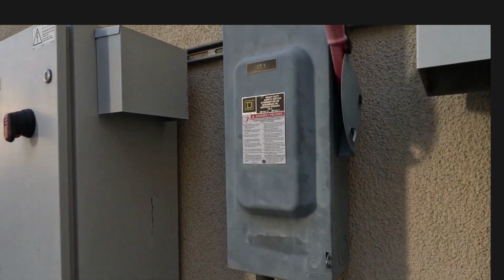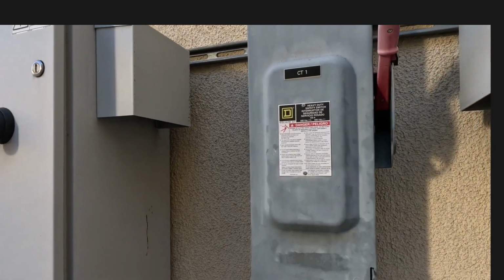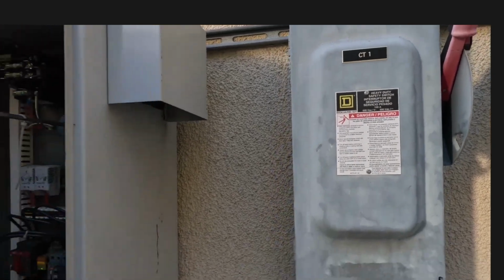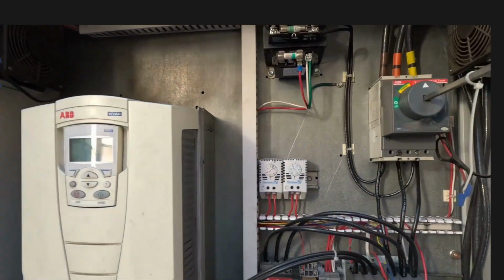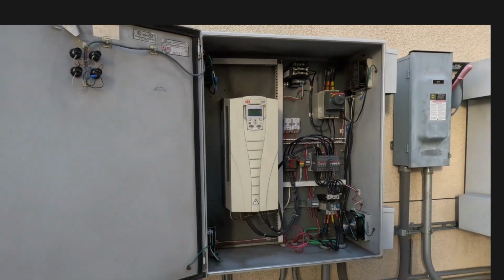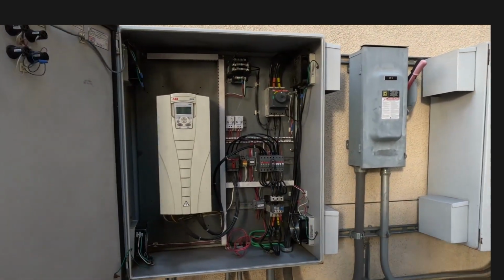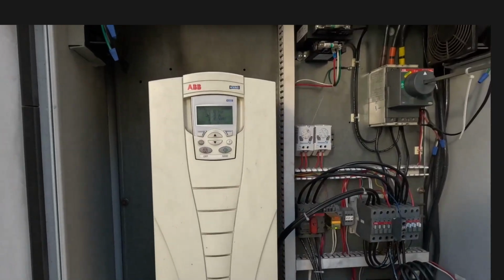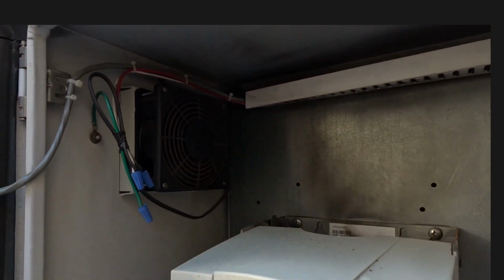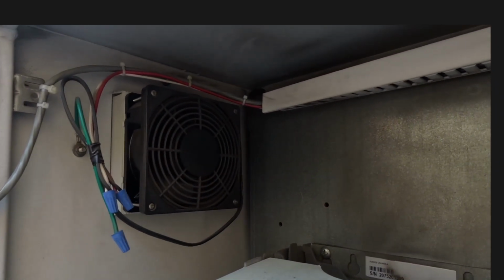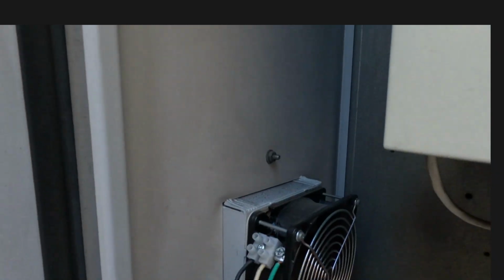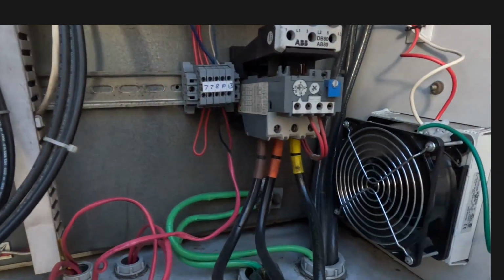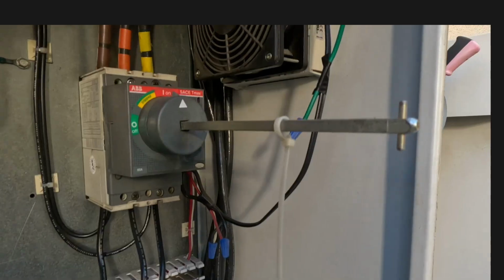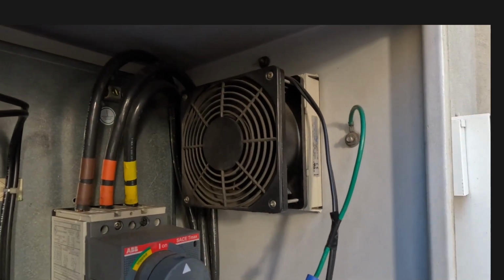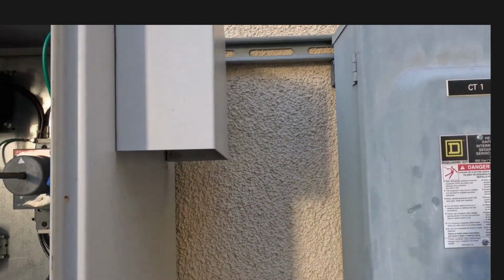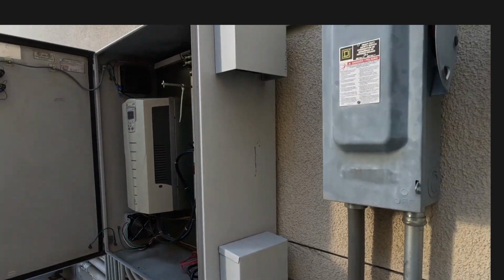Then here's your second cooling tower VFD. Here's the disconnect switch for it. This one's on. So you can see inside this electrical box where the VFD is located, you got a bunch of components in here, right? And then one of the things I wanted to point out was we need to be checking these little circulating fans, right? Some of them are exhaust fans and some of them are intake fans. We have to be able to inspect these fans and make sure they're running properly, because they're the ones that keep the cabinets cool for that VFD.